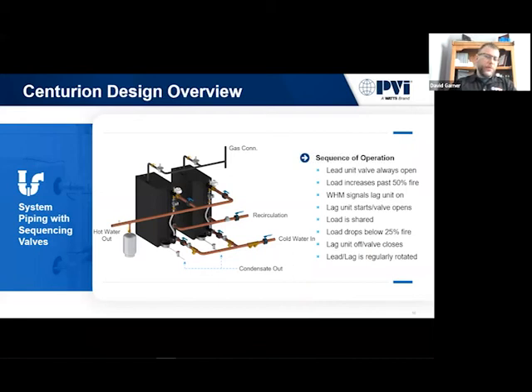And then from there, we'll go all the way up doing that for 16 units. It'll operate almost like a boiler plant, to where they'll all ramp up, ramp down together, kind of stage on, stage off. Once the firing rate gets down to about 25%, we have a little time delay there to help prevent short cycling, and just hopefully eliminate that factor and cycle that unit off and stage all the way down. If you get to about 100,000 BTUs, that's probably about what you might see on a recirc loss, maybe up to 200,000, based on the size of the building.